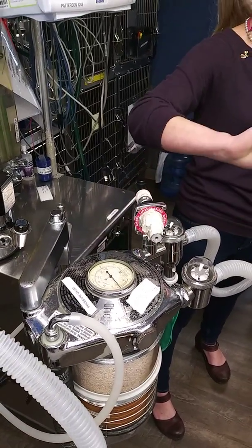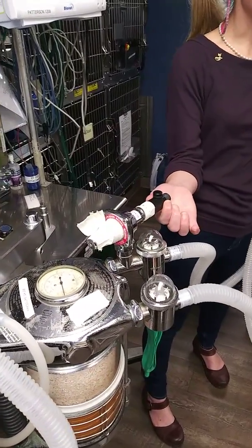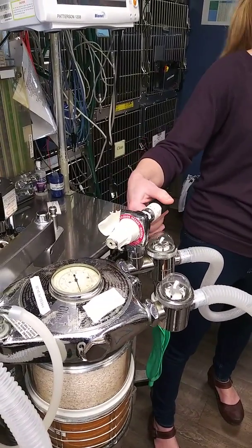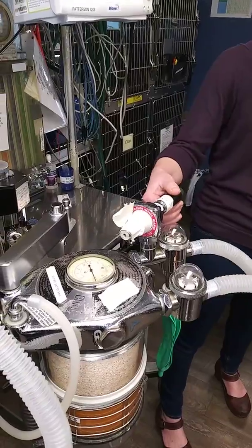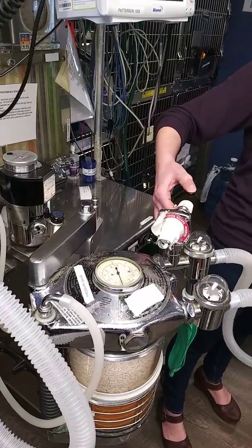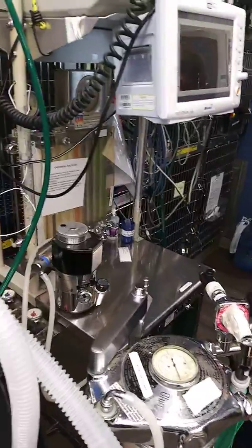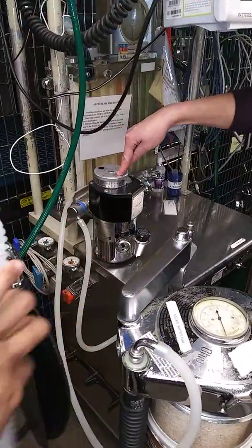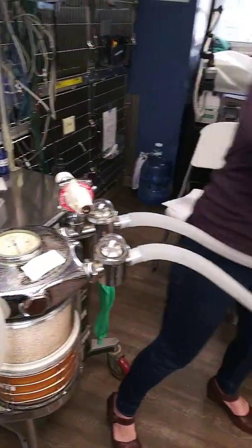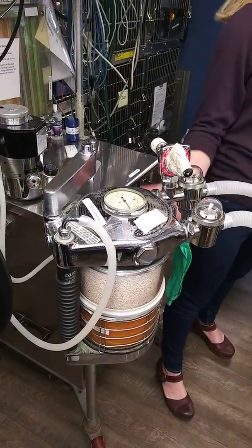We're not going to talk about the ventilator. So this is always in the open position, and this is called the pop-off occlusion valve. This is a safety valve that we use to deliver a breath to the patient. And then this would go to the scavenger. And there's notes in there about it. So again, oxygen comes in, into the vaporizer, out of the vaporizer, they breathe in, they breathe out, the CO2 is reabsorbed, then they rebreathe.